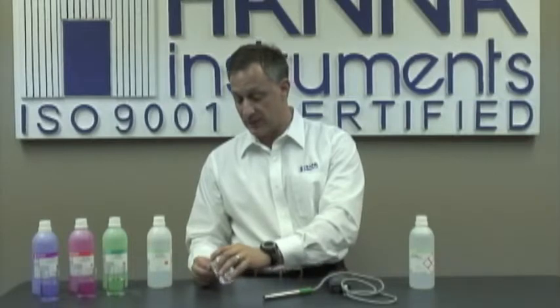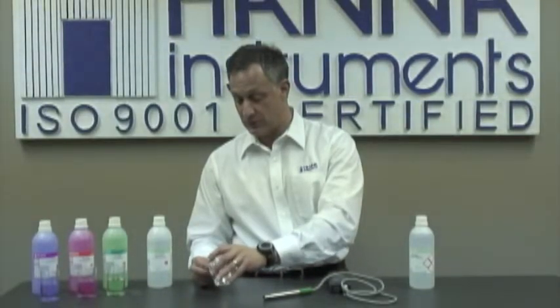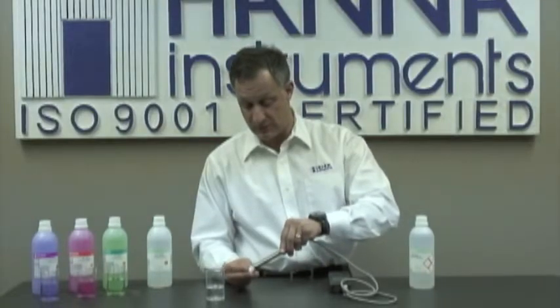One final note. After you're done using your probe, it's very important to keep it conditioned. What I like to do is simply take some storage solution, pour it into the cap that the electrode comes with. Now, if you don't have storage solution, it's okay as well to use buffers. So after you put the buffers or the storage solution into the cap, you simply place the cap onto the electrode and you're ready to go for the next time. Now, in case you ever have erratic readings with your probe, it could be due to some kind of buildup on it, and in that case, we have application-specific cleaning solutions.